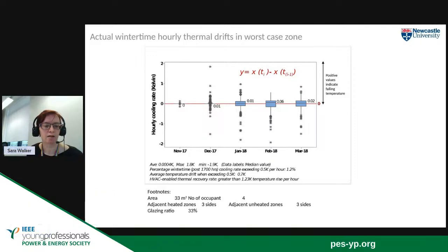And so for each of these months, we looked at how the building behaved, and we've done a box plot here. So the values are the median, and then you've got the second and third quartile, and then the first and fourth quartile in terms of the spread outside of the box plot. On average, over these months, we found that the cooling only exceeded 0.5 degree an hour for 1% of the year, 1.2% of the year. So the building is performing really well. It's cooling down very slowly, and it gave us the opportunity to offer demand response for up to 4 hours, no problem in terms of the extent to which the building cooled.